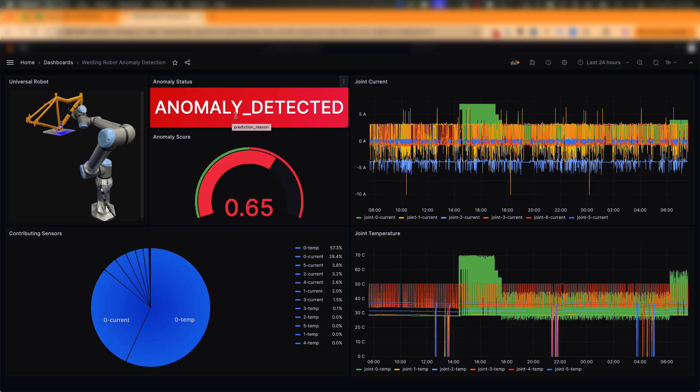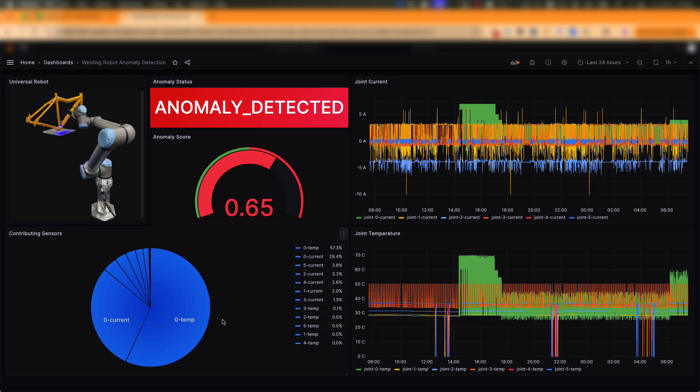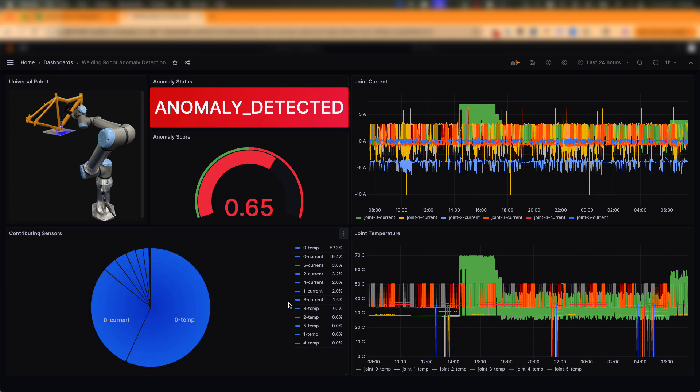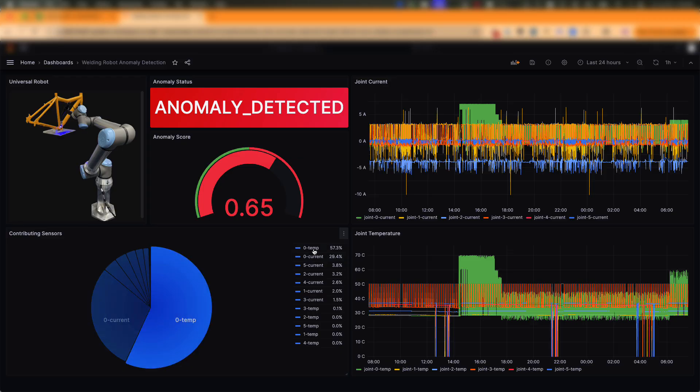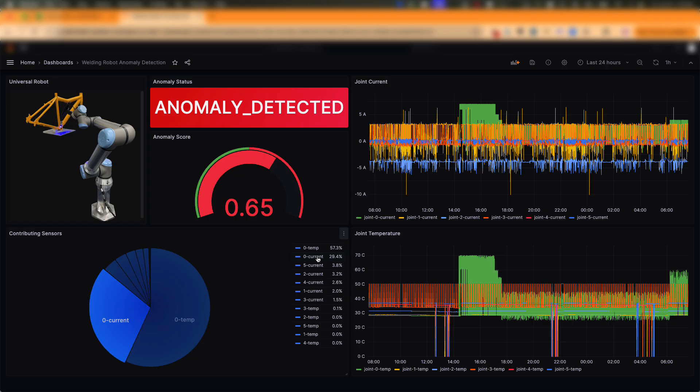Now this decision uses 0.5 anomaly score as a threshold, but you can define your own threshold depending on the criticality of the machine. SiteWise also provides model explainability, which is displayed in this pie chart. The pie chart shows the top contributing parameters or sensors to each decision. In this case, you can see the top two contributing sensors are the temperature and the current from joint 0. This really helps the operators and engineers to quickly diagnose and resolve issues. And that's the end of the demo.